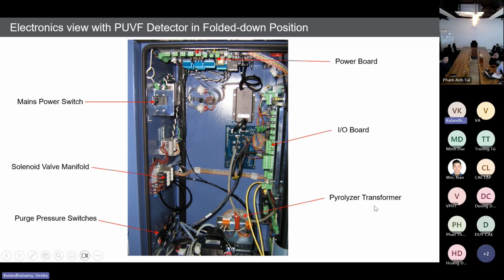Also, the pyrolyzer transformer, which controls the 1100-degree temperature through the heater power supply. The IO board is on the right side, and the power distributor board is on the top of the chamber. This is the main power isolation on-off switch. The Solenoid Valve Manifold assembly can be used for stream switching, calibration sample switching, and sample injection valve switching. The purge pressure switch is for the G purge. We have a Zone 1 X purge also. It's optional; based on customer requirement, we will provide G purge or X purge.